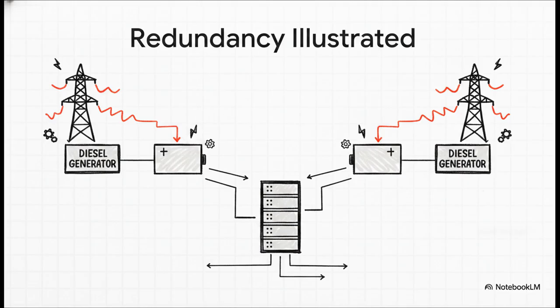Basically, it means duplicating everything. Instead of relying on a single piece of equipment, data centers use redundancy strategies like duplicate utility feeds, literally bringing power in from two entirely different utility grid substations. They install multiple UPS systems, multiple backup generators, and sometimes even completely duplicated electrical distribution paths. You'll often hear these high-reliability engineering strategies referred to with terms like N+1, or 2N design concepts.